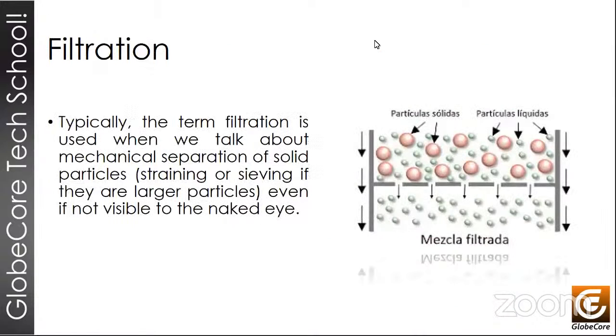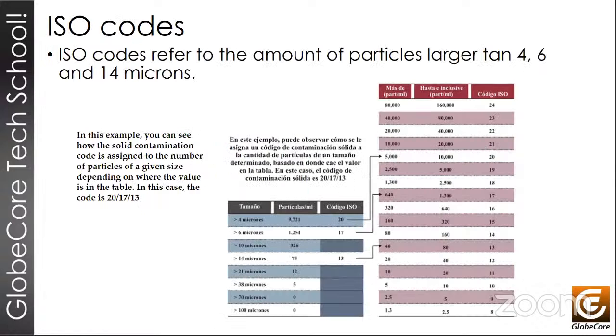So this will lead us to the next slide, please. So this will lead us to the ISO oil measurement system. And this system assigns us 3 types of particles. Actually, 3 sizes of particles. There are 4 micron, 6 micron, and 14 micron particles. Now let's see what those ISO codes mean.